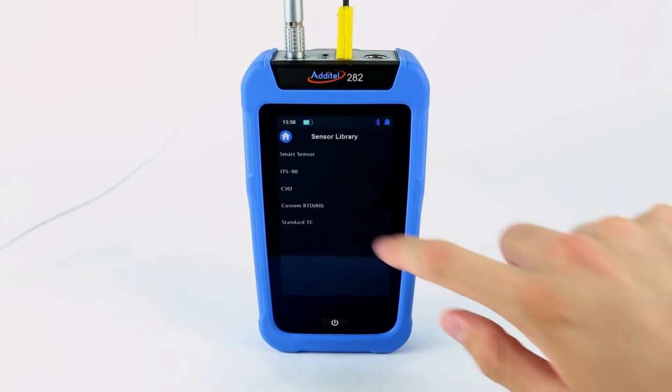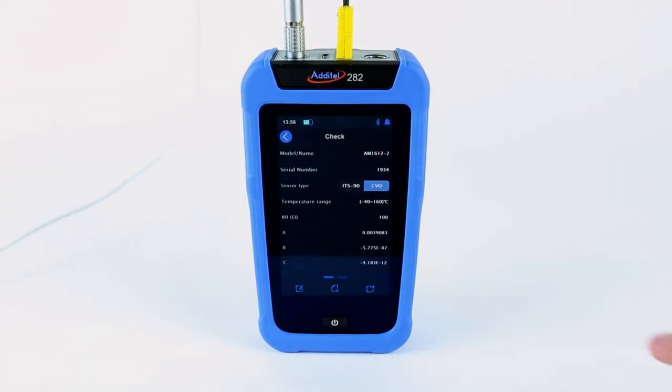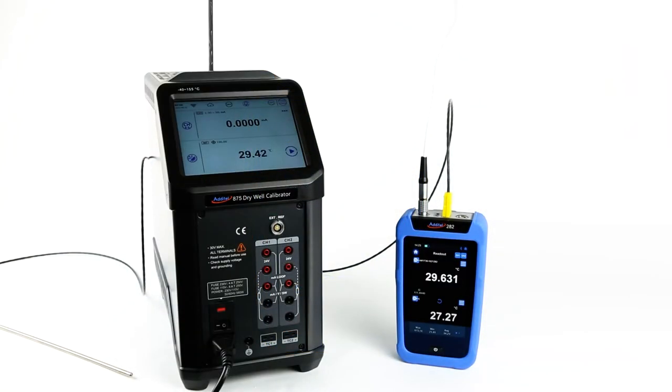The Additel Smart Connectors are capable of storing probe calibration information on board the probe to help prevent having to enter calibration coefficients, saving you time, money, and potentially incorrect measurements.